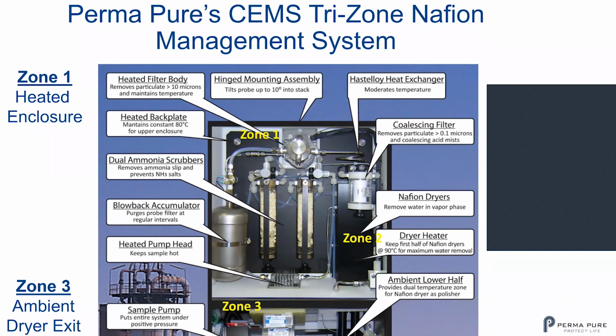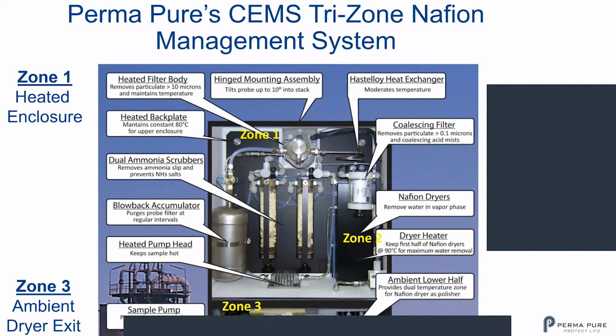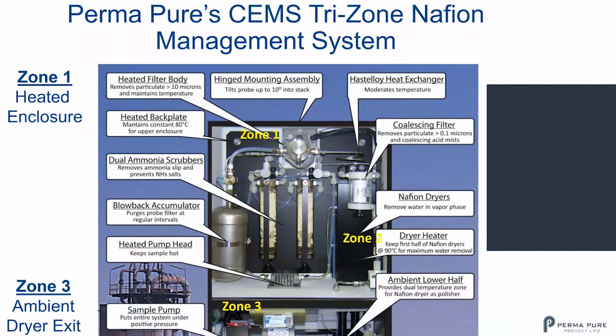So let's go back. Now that we have our clean sample, it goes into the heated portion of the dryer. If you've been on previous presentations, you know how important it is to heat the first portion of the dryer to make sure that we remove the water in the vapor phase and do not have any condensation in that sample stream. Not only do we recommend it to everybody else, we do this ourselves by building the heater into our own equipment. Here we're heating the first part of the dryer to 90 degrees C.